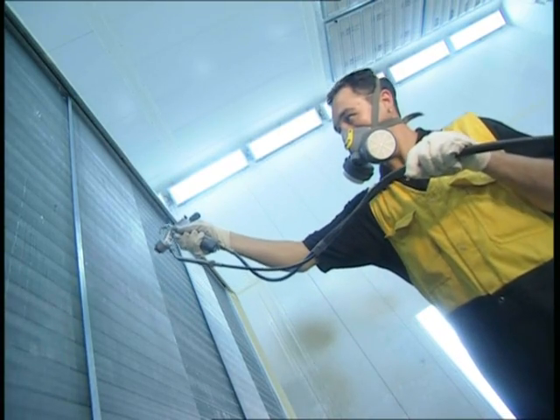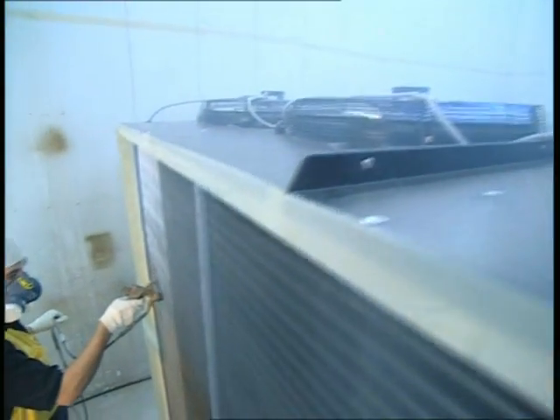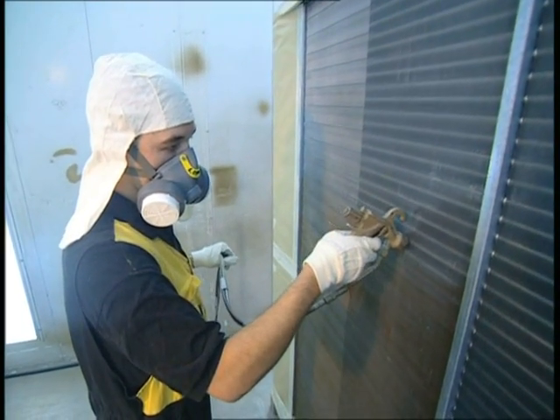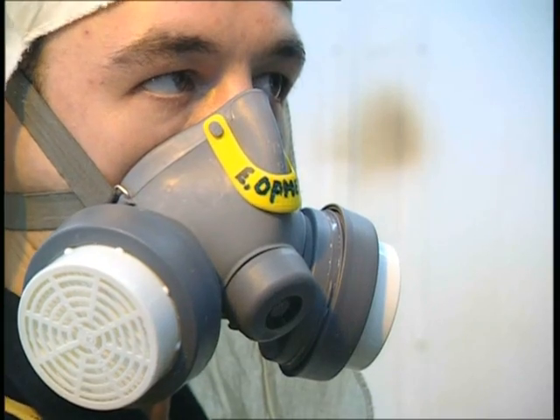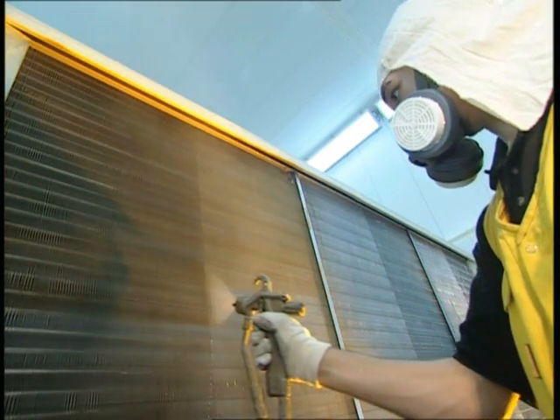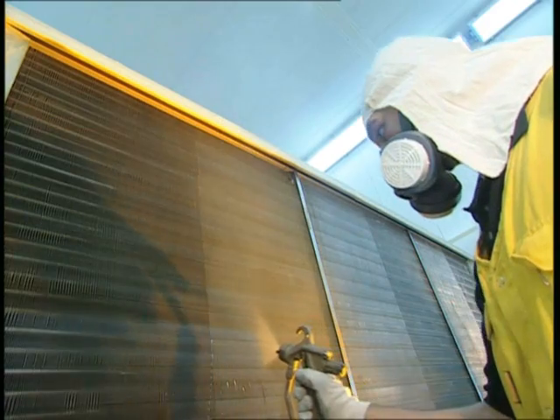To meet Blygold quality standards, the top layer must be penetrated completely and have an equal layer thickness, and the cutting edges must be covered sufficiently. The penetrating layer is sprayed on from a 45-degree angle. The total inner part of the coil is equally covered, and after a short drying time, the cutting edges are then also covered.